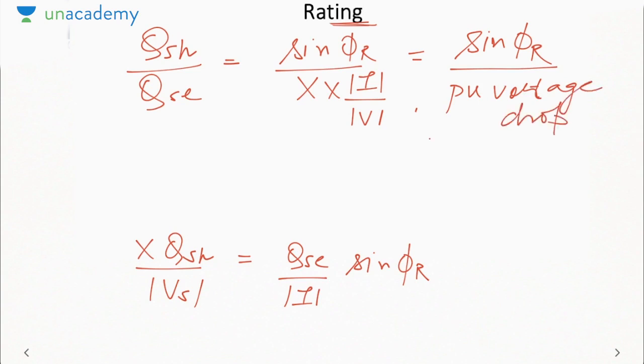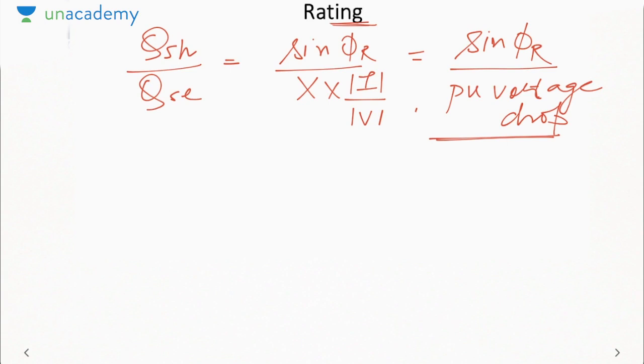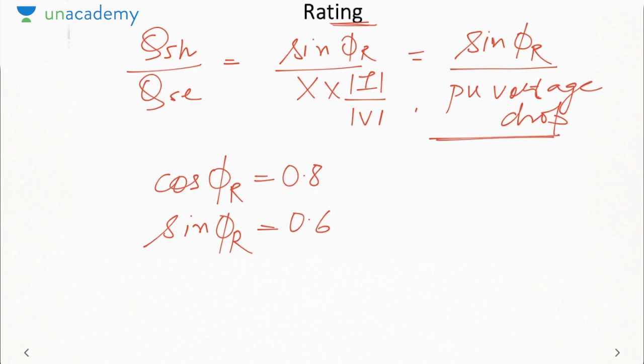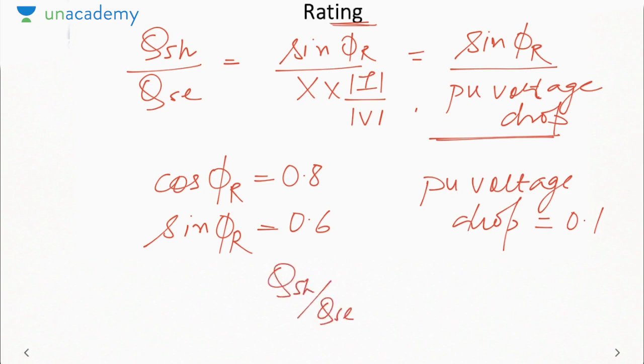Now to approximate this expression, we will consider some power factor. As you might have already seen in many problems, the most commonly occurring power factor is 0.8. That means sine phi r will be 0.6. Now the voltage drop in the line may be 10%, 20% at the most, not more than that. And anyways we have to keep it less than 5%, otherwise we have to use voltage control to bring it into that range. So let me say the PU voltage drop is 10%, that is 0.1. So Q shunt by Q series will be 0.6 by 0.1, that is 6. So Q shunt is greater than Q series.